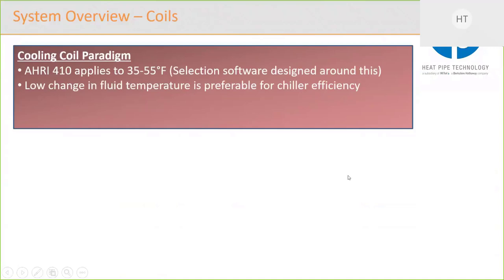Generally, we want to have a low change in fluid temperature, and that's best for the chiller to be as efficient as possible. That can be achieved by increasing the fluid flow, but that means more head drop in the system. And therefore, there's going to be a sweet spot at which you decide this is the optimal flow rate. Another thing that affects the optimal flow rate is the velocity that the fluid flows through the coil at. And it's important to keep a higher velocity so that you can keep that turbulence in the pipe and make sure that the heat transfer ratio is sufficiently high for an efficient coil.